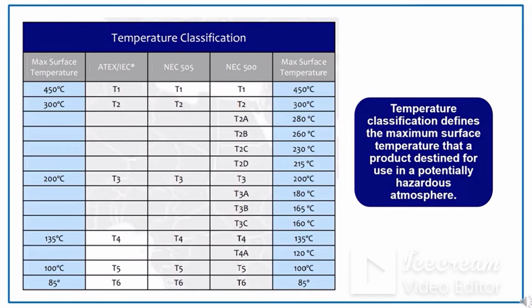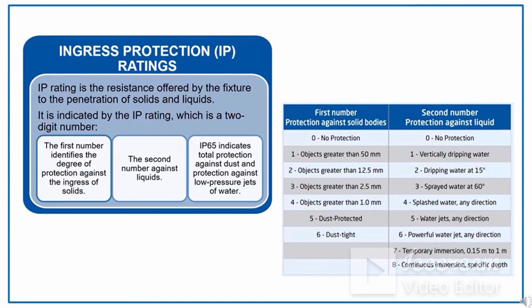Ingress protection or IP ratings. Ingress protection of equipment must be suitable for prevailing conditions at the point of use. IP rating is the resistance offered by the fixtures to the penetration of solids and liquids. It is indicated by the IP rating, which is a 2-digit number. The first number identifies the degree of protection against the ingress of solids, whereas the second number is against the ingress of liquids. An IP65 rating indicates total protection against dust and protection against low pressure jets of water.